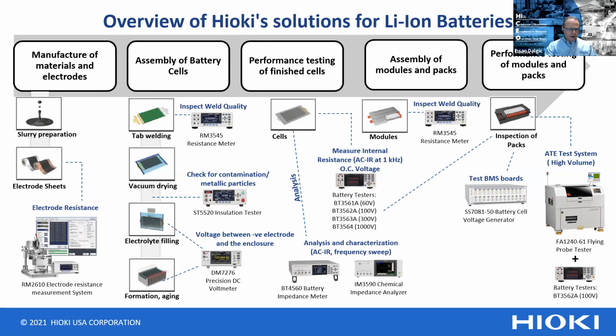And so for performance testing of the finished cells and for cell sorting, we have a number of different test solutions. The battery testers, for instance, test the AC-IR method using a 1 kilohertz test signal. And for doing more in-depth analysis, for doing frequency sweeps, the Nyquist plots and Bode plots, we have two systems, the battery impedance meter and chemical impedance analyzer that can create a Nyquist or Cole-Cole plot so you can see the state of health of the battery. And then finally, we have the assembly of the modules and then performance testing of modules and packs. And that could involve inspection of the packs, inspection of the battery management system, the circuit that goes into the packs. And we also have high volume test capability using ATE test solution.